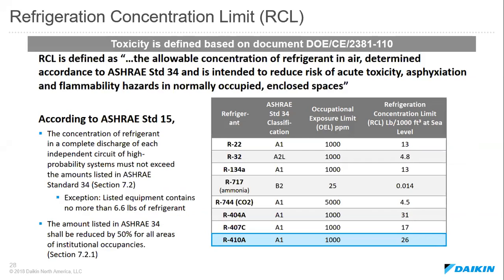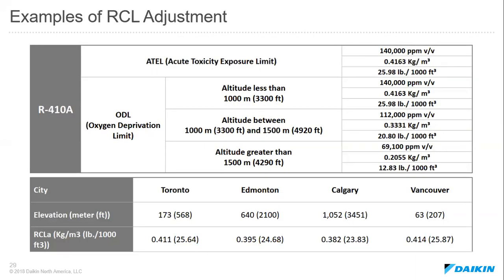So when we're looking at R410A, which is utilized in most VRF systems, that concentration level at sea level is 26 pounds per 1,000 cubic feet. And this refrigerant concentration level may be limited or reduced to 50% if we're located in an institutional facility. And so on this chart, I'm giving some examples of the amount of refrigerant that's allowed if we were at sea level.